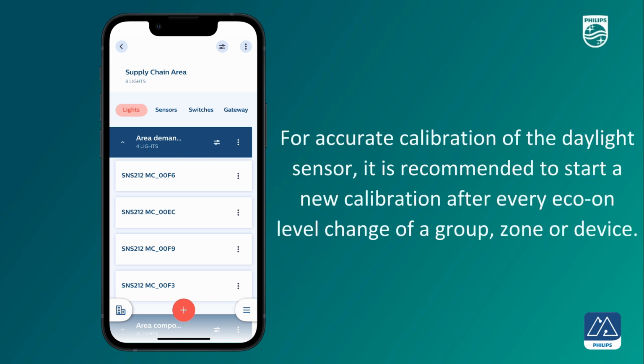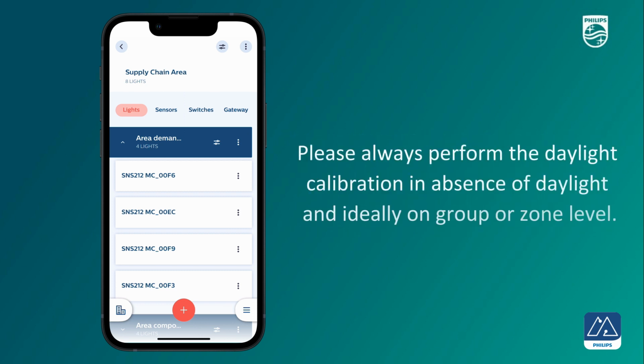For accurate calibration of the daylight sensor, it is recommended to start a new calibration after every eco-on level change of a group, zone, or device. Please always perform the daylight calibration in absence of daylight and ideally on group or zone level.